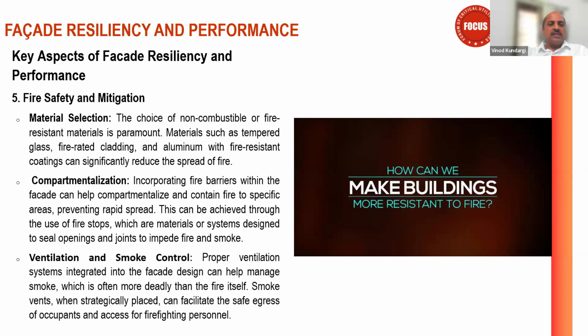Then next is ventilation and smoke control. During fire incidents, it's often the smoke that creates more casualties, because there is no proper visibility, and both rescue personnel and trapped people find smoke a major hindrance for visibility, so they don't know where to go or where the exit is. There are mitigation strategies like smoke control actuator vents, so that in case of fire, the facade opening is connected to the IBMS, which sends a relay and automatically opens the vent where there is a fire alarm.